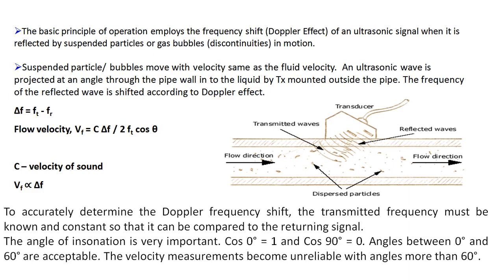The suspended particles or bubbles move with the same velocity as the fluid. An ultrasonic wave is projected at an angle through the pipe wall into the liquid by a transmitter mounted outside the pipe. The frequency of the reflected wave is shifted according to the Doppler effect and measured by the transducer using the pulse echo technique. The flow velocity is given by: vf = c × delta f / (2 × fd × cos θ), where c is the velocity of sound, delta f is the frequency shift, ft is the transmitted frequency, and θ is the angle of inclination of the transducer.